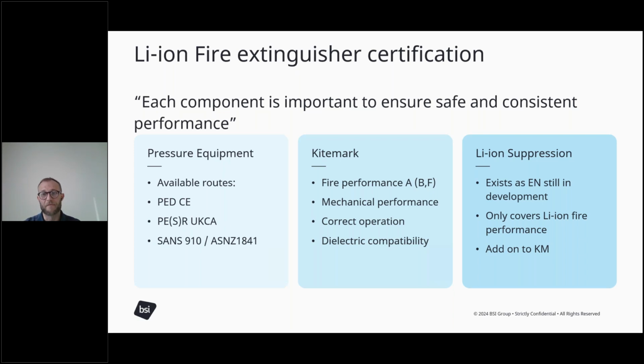The route to certification is shown on this slide, left to right, starting with pressure equipment certification, as it's the minimum regulatory requirement for placing fire extinguishers on the UK and EU markets. Next is standard Kitemark certification in accordance with EN3 as a requirement, and it's a really tough requirement as well. Only once that's in place do we have the compliance certificate, like a bolt-on for the lithium-ion fire performance. It's important to note that the fire suppression performance documented on our certification is for the actual unpackaged battery as tested.